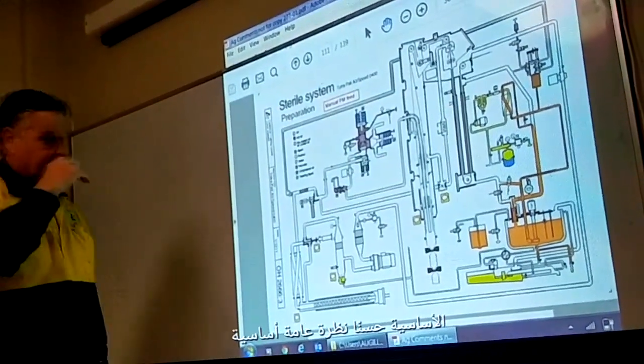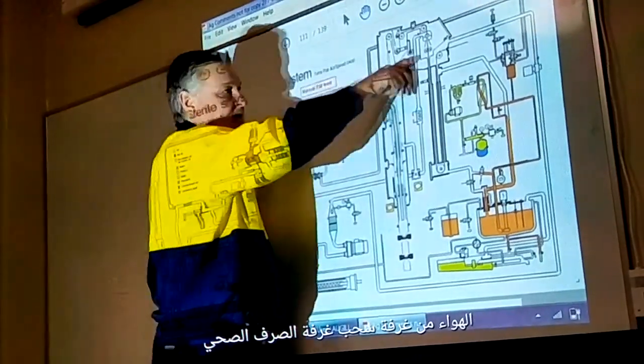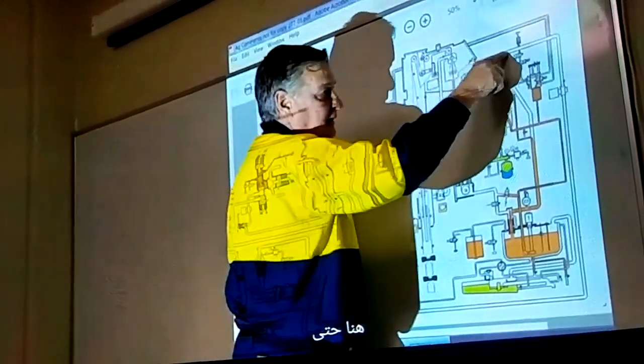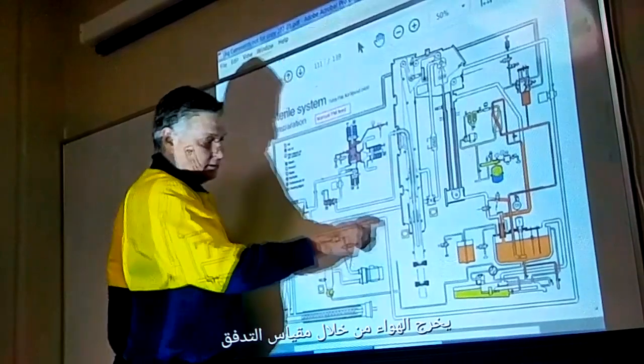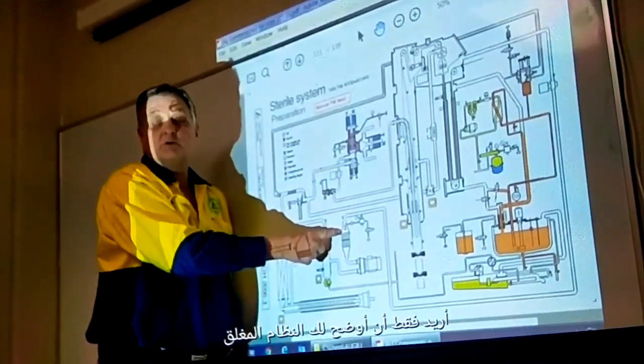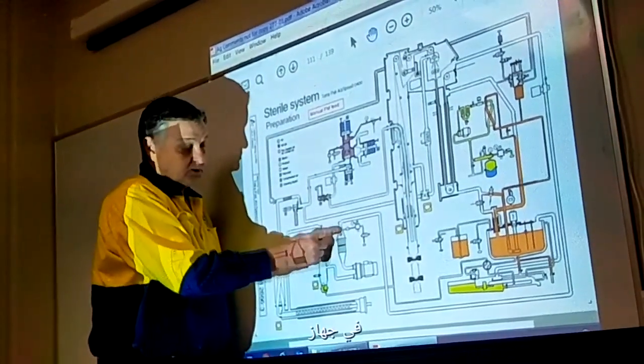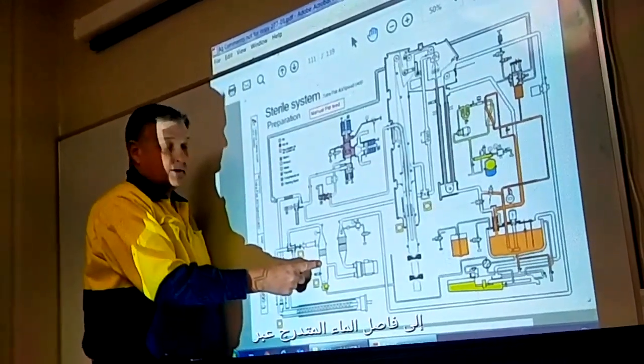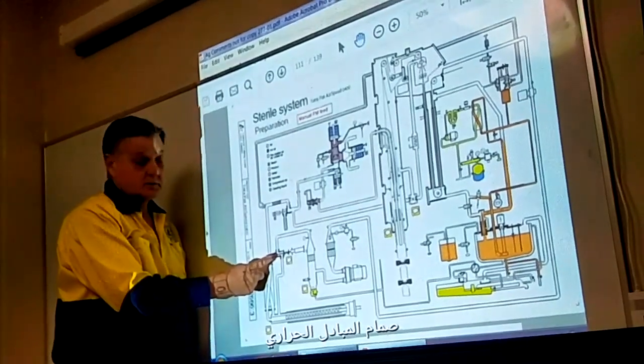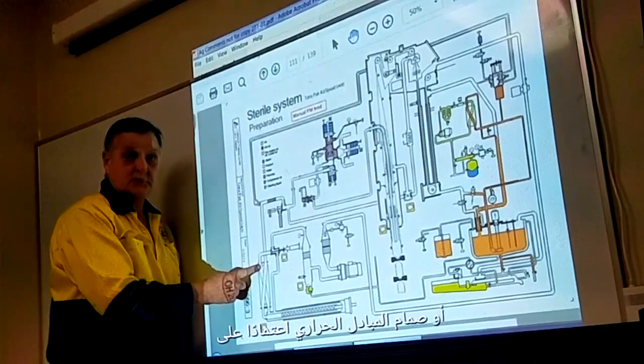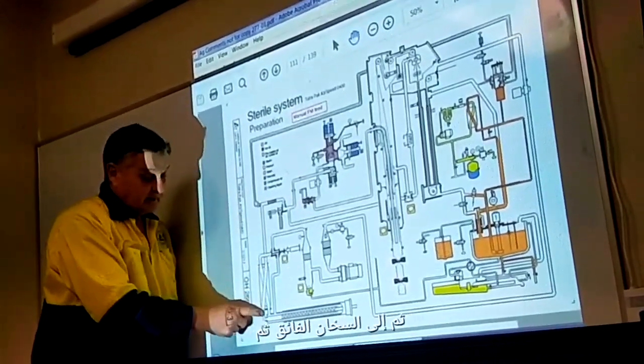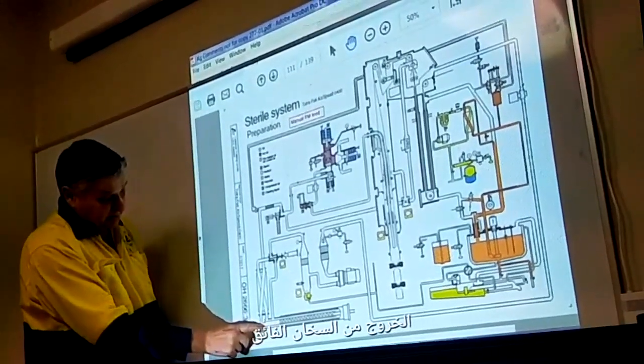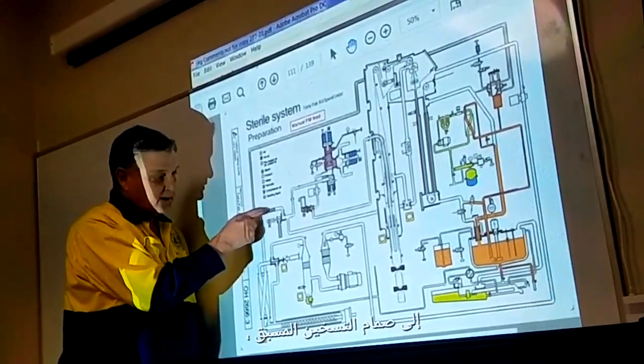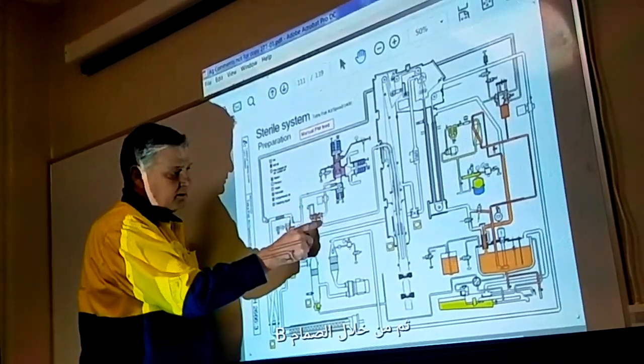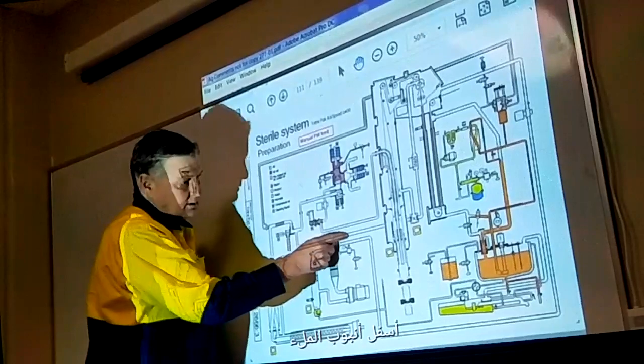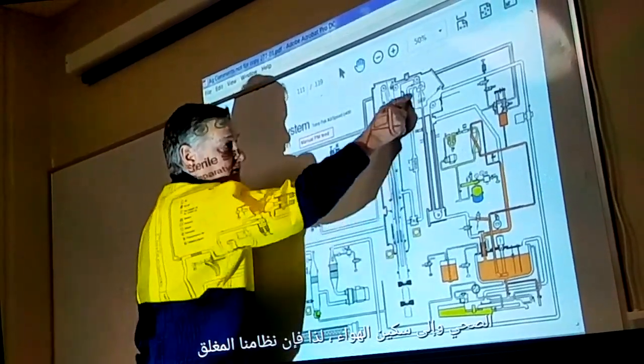Okay, think about the basic overview. Remember in the basic overview, we drag air from the aseptic chamber, drying chamber, here. So air out through the flow meter, down to the scrubber. I'll explain this in more detail later. Okay, I just wanted to show you the closed system. Into the scrubber, scrubber to the compressor, compressor to water separator via the heat exchanger valve, or heat exchanger, depending on what step we're in the machine. Then into the superheater, then out of the superheater to the preheating valve, then through the B valve, down the filling pipe, and into the aseptic chamber, and into the air knife.